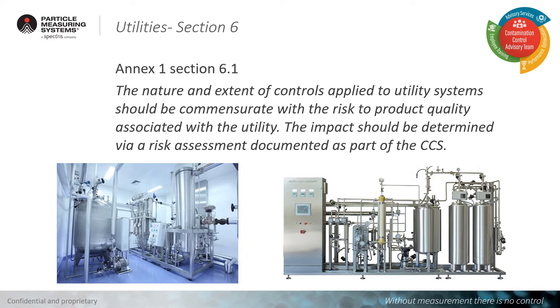We will conduct a scientific evaluation of the characteristics and functionality of each point. The goal is to define our QC sampling points and points of use. We want to make sure we consider any unused points and do an evaluation of each of the valves regarding slope, positioning, and disinfection, as well as how we manage our piping — how we flush, disinfect, etc. This will also help us determine the appropriate sample handling technique and sample containers in order to develop our sampling plan.